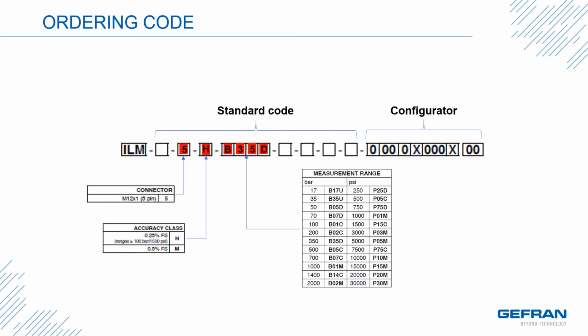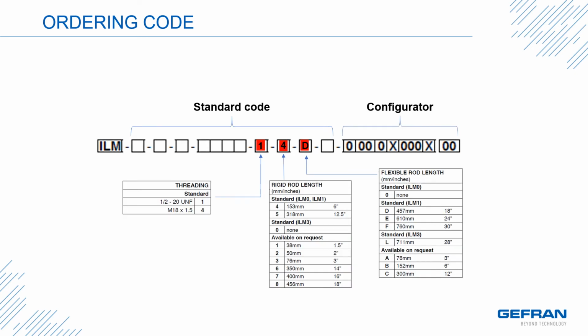The next series of blocks in the order code indicate the connector type, of which there's only one choice, and that's the M12 5-pin connector. The accuracy class has two choices, either 0.25% of full scale or 0.5% of full scale, and then the pressure range. The next three blocks define the thread, the rigid stem length, and the flexible stem length.